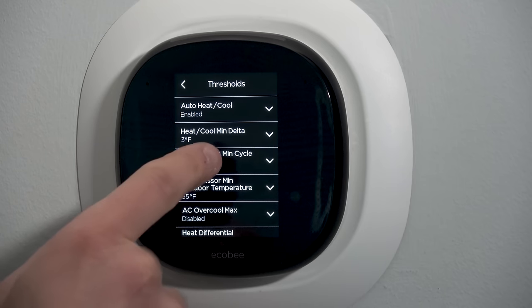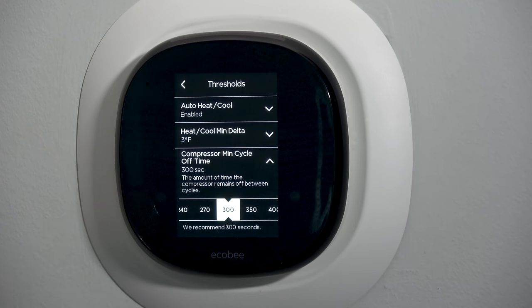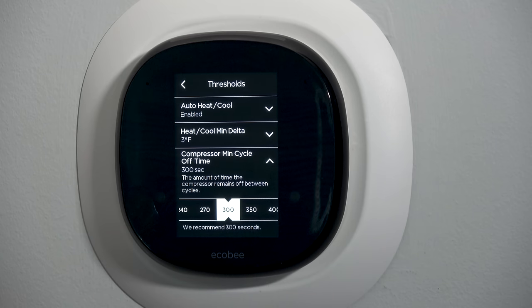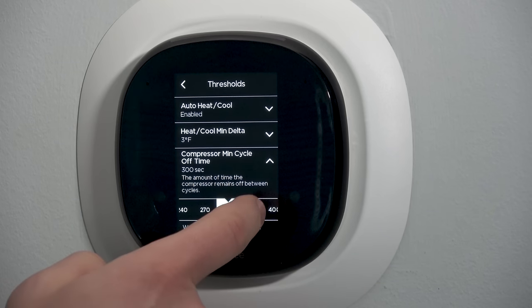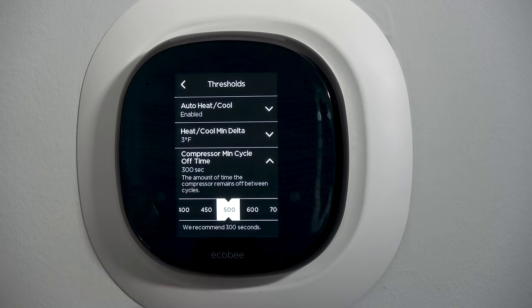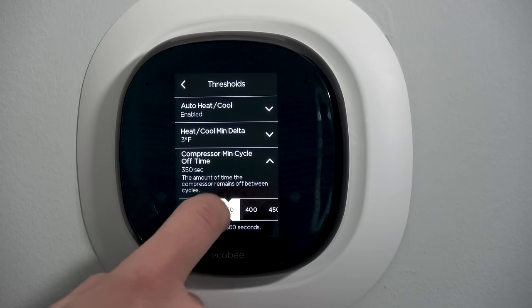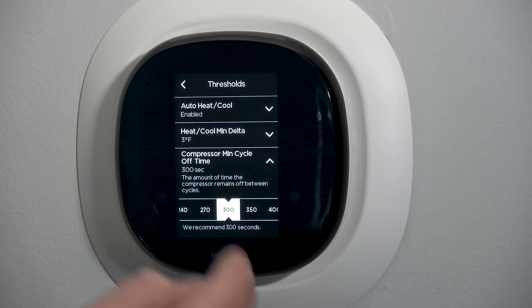Compressor minimum cycle off time: 300 seconds, which is five minutes. That's the amount of time the compressor remains off between cycles — we don't want the equipment short cycling and the compressor getting beat up. Once it goes off it'll stay off for a minimum of five minutes. The only time you might want to change that is if you're having humidity control problems due to oversized equipment — you might make it a bit longer to force a longer run cycle, but at the cost of temperature comfort.